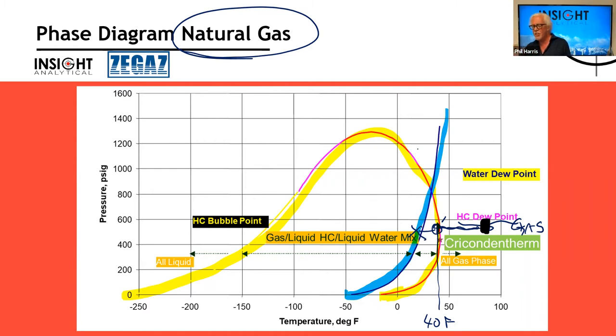We can use this effect to figure out the hydrocarbon dew point and the water dew point of the stream. We just need to cool it down and in some way be able to detect that liquid has started to drop out and identify which liquid it is. The more complex the stream, the more heavier hydrocarbons are in the stream, the further it goes away from being, say, a pure methane or an ethane-methane stream, the fatter this phase envelope may get.